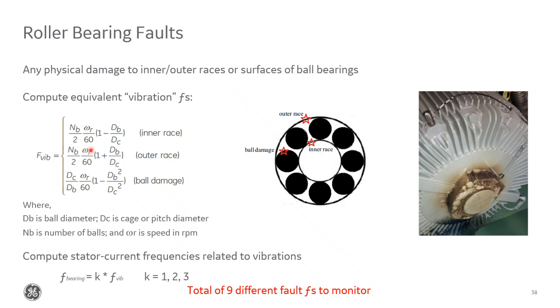But the gist of it is that for bearings, we calculate the equivalent vibration frequency. Because if you have a bad bearing, it's going to cause some sort of a physical vibration. We have a different formula for the inner race, outer race, and ball. After we calculate what the equivalent vibration frequencies are, we determine what frequencies this would show up at in the stator current signal down here.